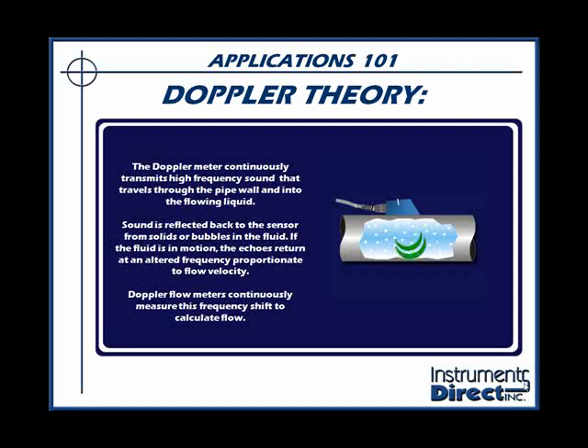The way this works is the Doppler meter continuously transmits high-frequency sound that travels through the pipe wall and into the flowing liquid. Sound is reflected back to the receiver from the suspended solids or bubbles in the process liquid. If the fluid is in motion, the echoes return at an altered frequency proportionate to flow velocity. Doppler flow meters continuously measure this frequency shift to calculate your flow.